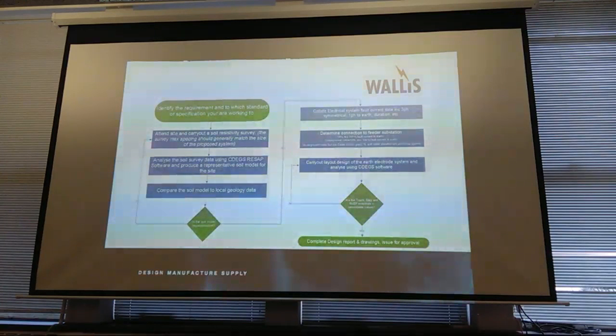You then need to collate, as I say, your electrical data, your three-phase symmetrical fault currents. Again, I'll come on to that and the reason we need that. Single phase to earth durations, etc. You also need to determine whether it's underground fed or overhead line fed. The reason behind that is, if you've got an overhead line fed standard wood pole 3-wire construction, it is literally 3 wires. There is no earth wire, there is no neutral wire, there's no return. So all of the earth fault that you have at your substation will go into your earth electrode system. Whereas if you've got a cable connected system, and I'm talking like 100% cable connected now, you will have the cable sheath or the armour or whatever connecting your site back to the source. So a percentage of any fault will go back up that path as well. So you have to do the fault current split.